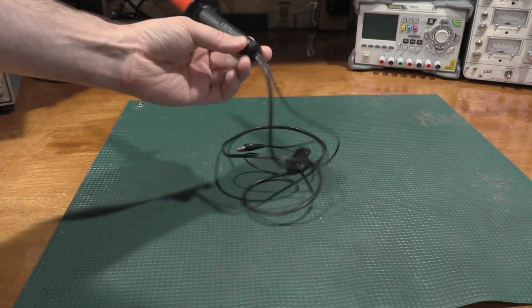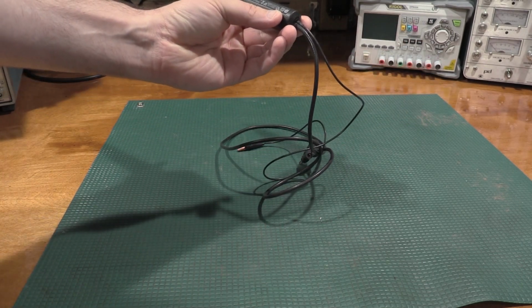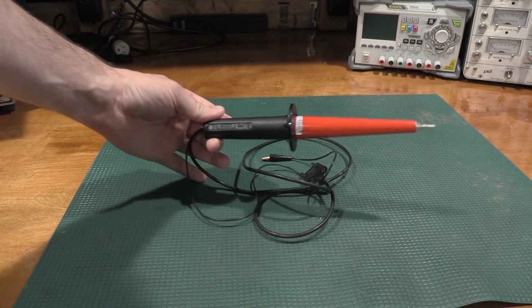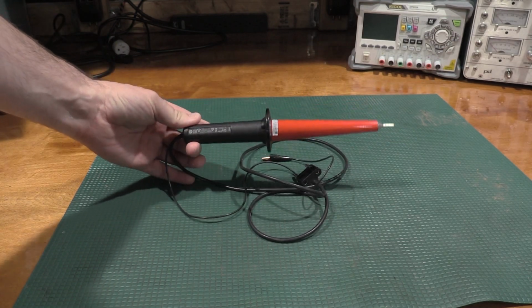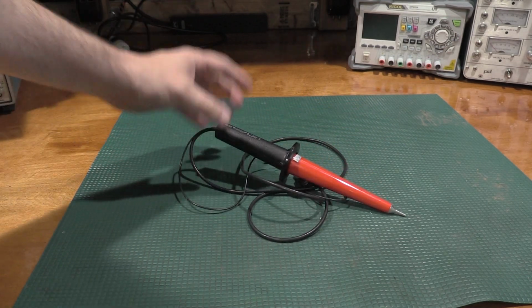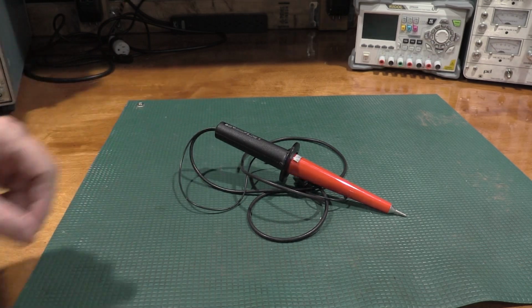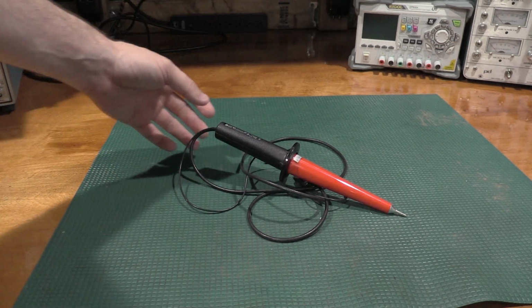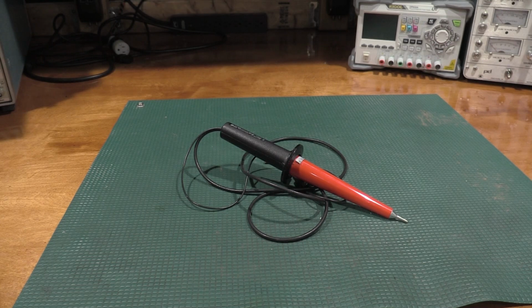Right here on the bench is my Fluke 80K-6. I believe this is a 6 kV probe. They do make two probes larger than this. This is actually the small one. I did check the 80K-6 is good to 6 kV. So it's right in the nice sweet spot where I'm taking measurements on the scopes where I need to measure the 4,000 volt rail and things like that.